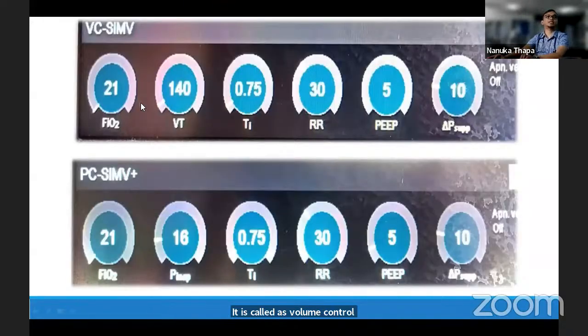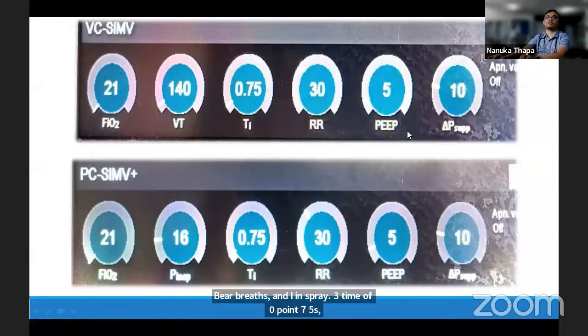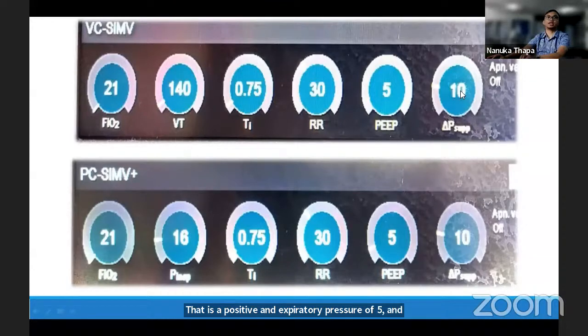In the above diagram, this is the volume control. Here we set the FiO2 of 21% and tidal volume of 140 ml per breath, and inspiratory time of 0.75 seconds, respiratory rate of 30, a PEEP, that is a positive end expiratory pressure of 5, and the delta P, which is the pressure support of 10. How do we get this delta P of 10? We'll go later to pressure control.